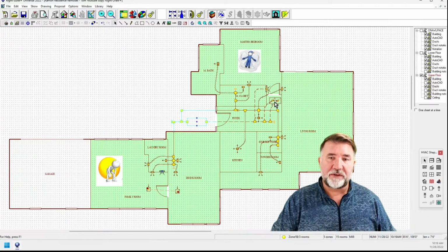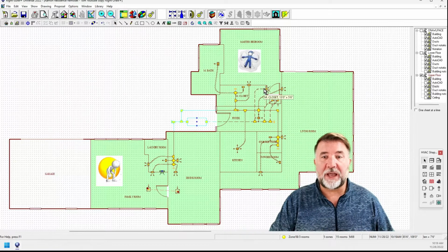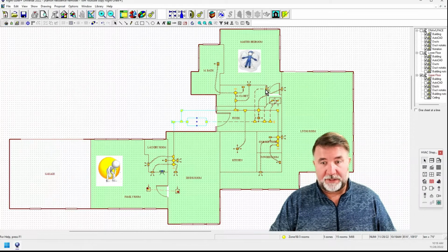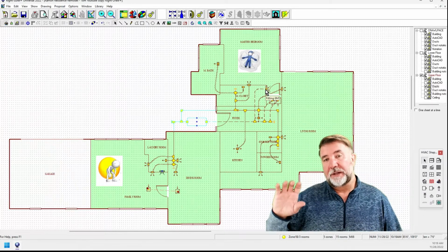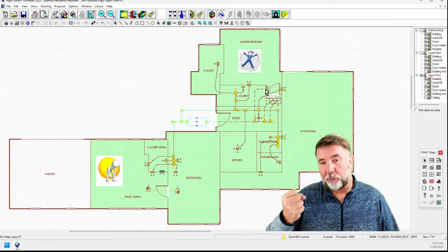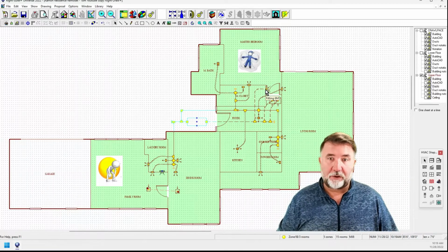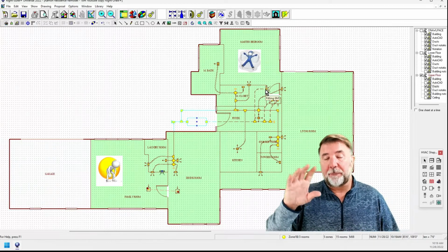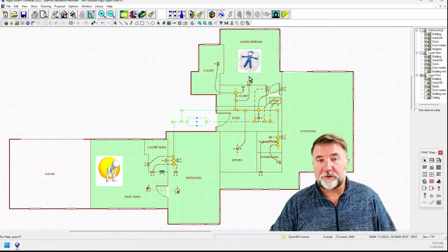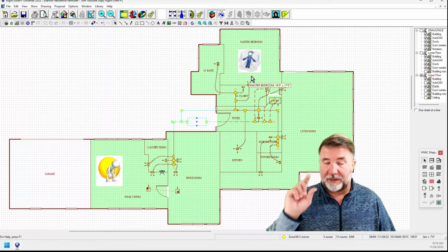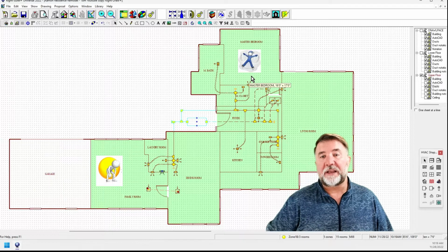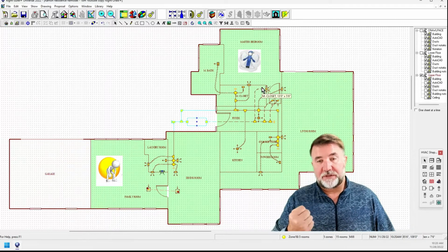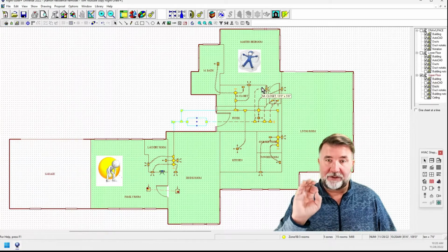And the other part of this is it allows us to actually put a damper in this. What that allows us to do is regulate the amount of return that's coming out of there as well. Again, remember I said, based on pressurization and whatnot, that could change. So if I only want 200 CFMs going into this room, I want to keep it under a slight positive pressure, I can set the return where it's pulling about 180, 190 out. And that helps to truly balance those rooms.